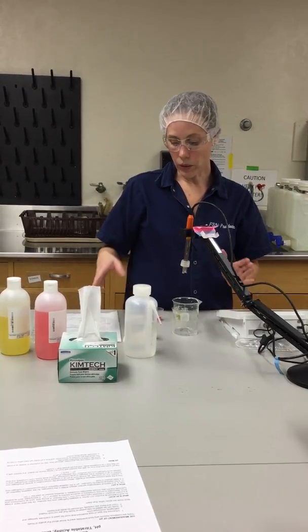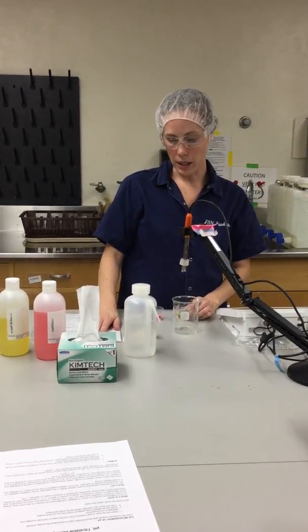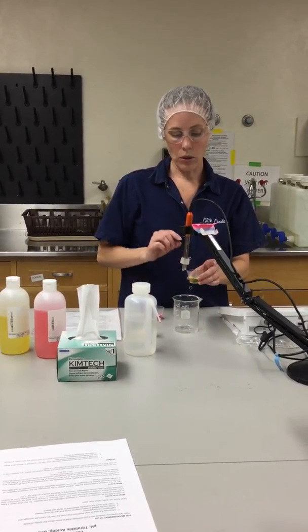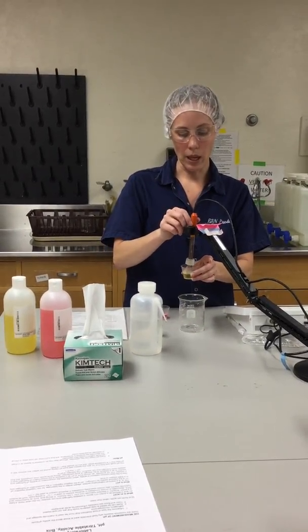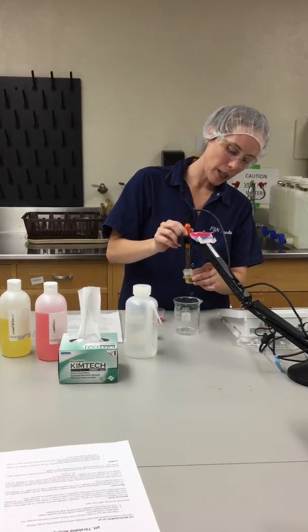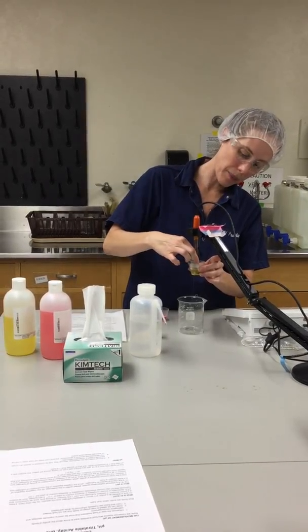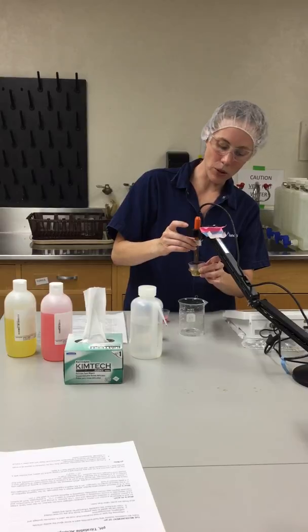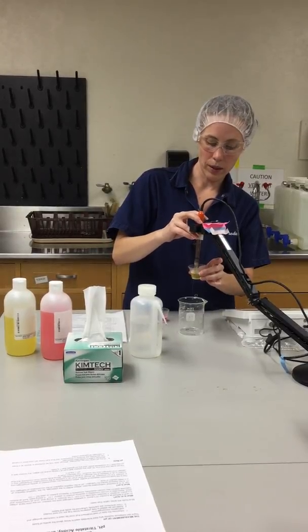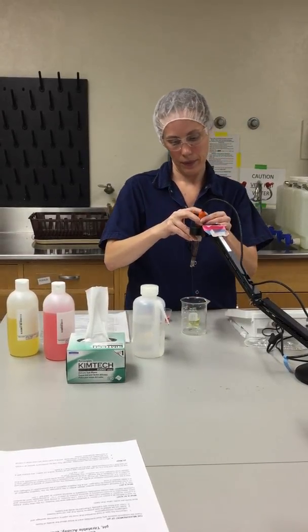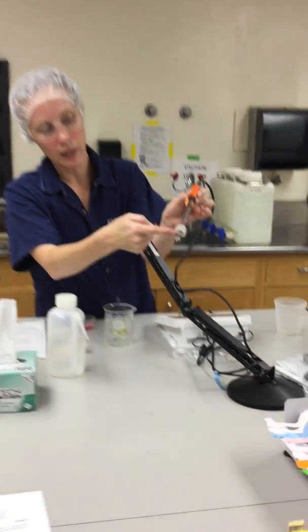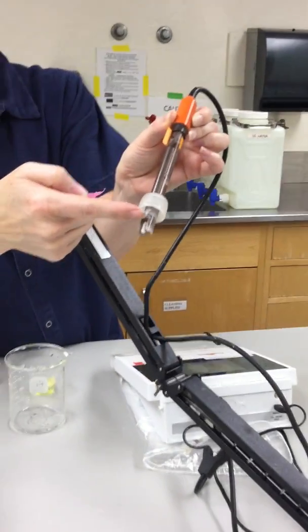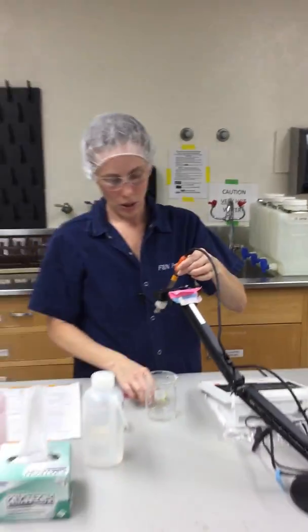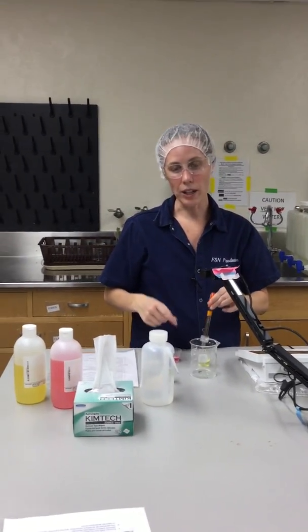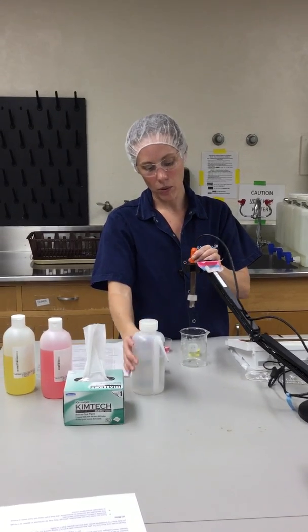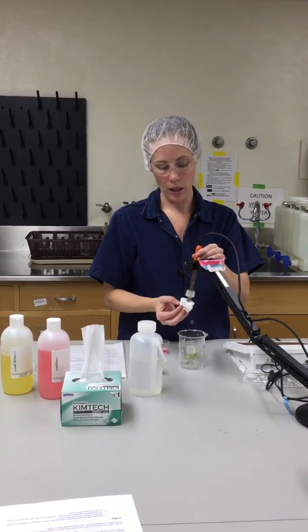So just briefly, and please make sure you follow these step by step, the meter is going to ask you to put the probe inside one of the buffers, and you're going to want to make sure that the probe is all the way submerged up to, let me show you here, up to this line here, and then you're going to hit some buttons.